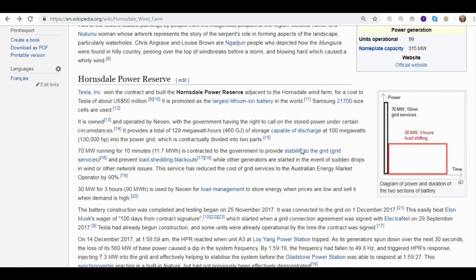And the battery has enough capacity to store 129 megawatt hours of energy and discharge at 100 megawatts into the power grid, and it's divided into two parts. The larger portion of this is contracted with the state government of South Australia to have 70 of the 100 megawatts running for up to 10 minutes to provide stability to the grid and prevent load shedding blackouts, and enabling the starting up of other generators when they have to stop for some particular reason.